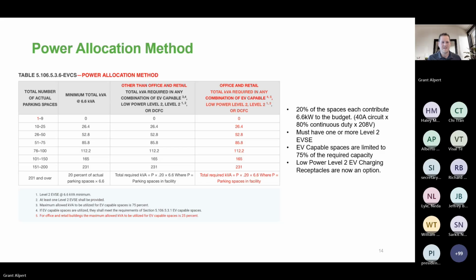So you start with the number of parking spaces you have. We'll start with 10 to 25 again. You multiply the number of parking spaces by 20%. And that 20% then gets multiplied by 6.6 kilowatts. So that's basically a 40 amp circuit, 80% continuous duty and 208 volts, which is like a baseline level 2 EVSE. And that's your minimum total kVA required for the parking lot. And from there, you can fill it out however you want.